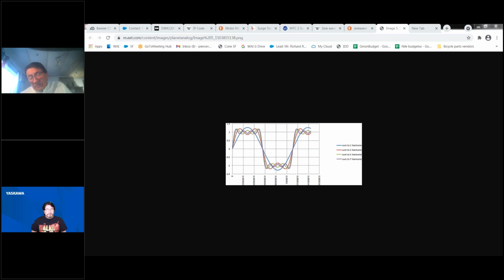Looking into it more, and I think to their credit, Franklin did some good work here. We realized that for a variety of reasons, these motors were failing thermally. They were overheating. Now, the initial thing that I got, not being in the mix as much as Craig was, is that these motors, because of their lower inertia, don't ride through the harmonics of the waveform that they're receiving from the VFD as well as a big fat above ground turbine motor, because turbine motors are NEMA motors and they tend to be shorter and wider, therefore they have big inertia. And that inertia helps them to ride through the aberrations that are associated with this waveform that you see on your screen.